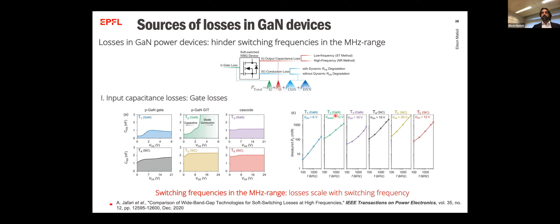The integration of this determines how much losses we have when switching the device. If we want to go to the megahertz range, we need to look at the effect of CISS, the input capacitance, on the total losses. Even though GaN should have a much lower loss compared to silicon carbide, depending on the technology this might not be the case. So we need to be careful what we are selecting, since not all gallium nitride matches the theoretical definition of it.